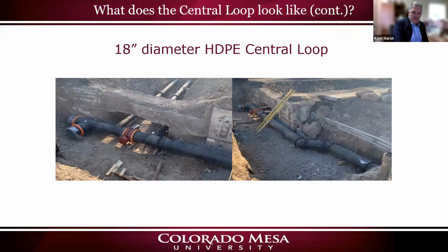These pictures show the central loop piping, which is at least 5 feet below the ground, below frost level. The big pipe is an 18-inch diameter pipe, and the smaller connecting pipes are between 10 and 12 inches in diameter. Depending on the load in any particular part of our system, the pipes serving buildings within that micro loop may be as small as 10 inches, while our central loop pipes are 18 inches in diameter.